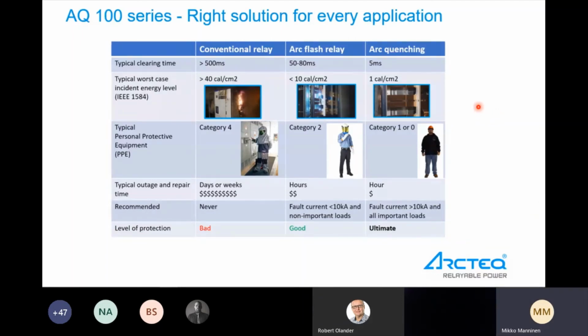And then something from this. This is from the IEEE committee, these calories and arc energy calculations. So this is one example that IEEE 1584 gives the calorie values, and then it goes to a certain category, and that category will tell what kind of overalls people have to wear. And with arc quenching, these calories will be in the best category 1, or actually category 0 no longer exists, so it will go to category 1.